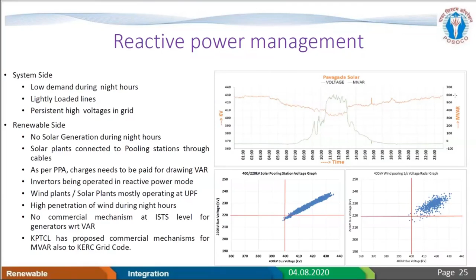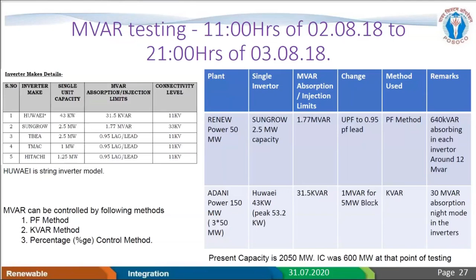We wanted to understand whether it is a problem of PPA or whether there is feasibility of MVAR. We tried to do MVAR testing at Pavagada, where we have tested it. We understood that there are three methods: PF method, KVAR method, and percentage control method. And here the table indicates how much capacity each inverter has. Like Sungrow, for a 2.5 megawatt individual inverter, 1.77 MVAR is the absorption capability. It's a very good capability. So we have tested over here.